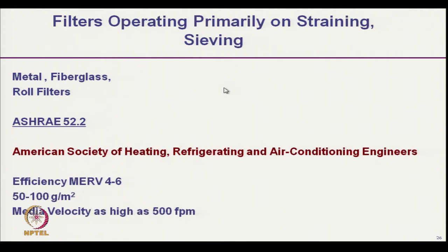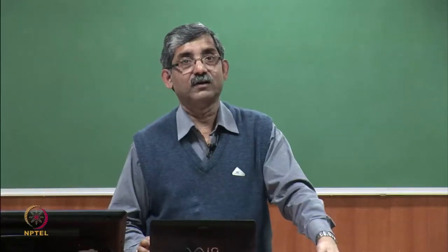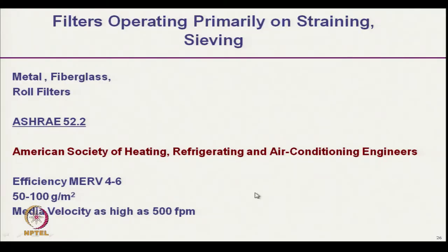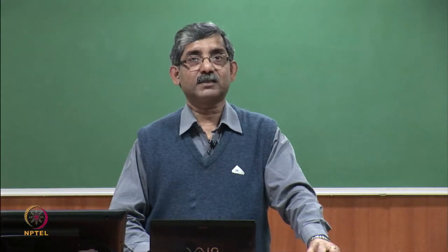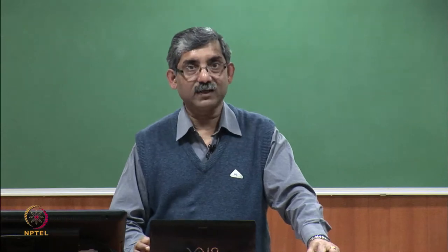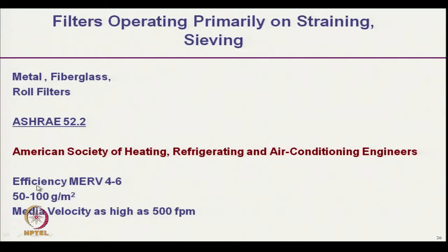Examples of straining-type filters include metal, fiberglass, and roll filters. As per ASHRAE Standard 52.2 — ASHRAE being the American Society of Heating, Refrigerating and Air Conditioning Engineers, which forms standards for filters — the efficiency for this straining-type filter is at MERV level 4 to 6.